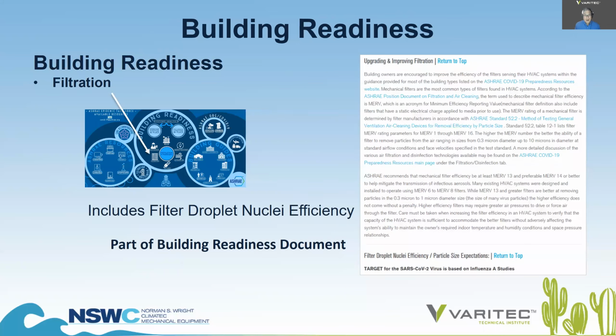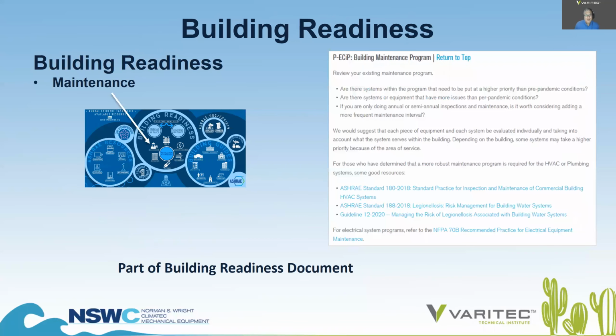Filtration. There's quite a lot that the building readiness guidelines have to say regarding upgrading and improving filtration. What are the considerations? How do you decide, based on a loaded filter, what sort of anticipated added static pressure might be incumbent upon that system, and whether or not you have the capacity in your air handlers to meet those requirements?